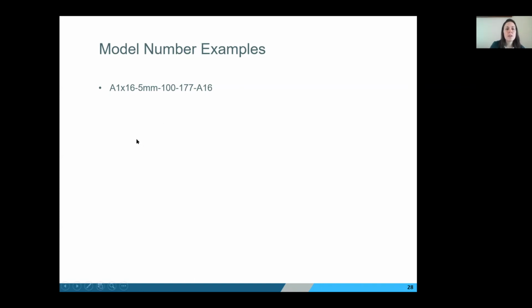Here's an example. Let's make sure we understand. It's an axial array with 1 shank, 16 sites on the shank. It's 5 millimeters long. The sites are spaced 100 microns apart, and the site area is 177 square microns, and we have an Acute 16-channel package. So we don't have a fancy site layout. That means this is linear. We don't have a shank spacing because there's only 1 shank, so you don't have to leave a blank space or something like that. This would just be interpreted that way.